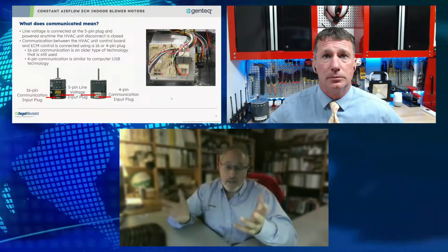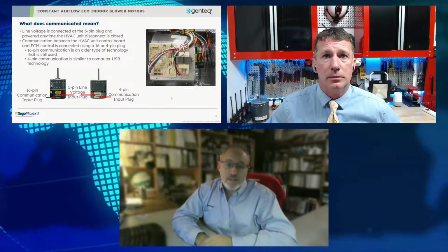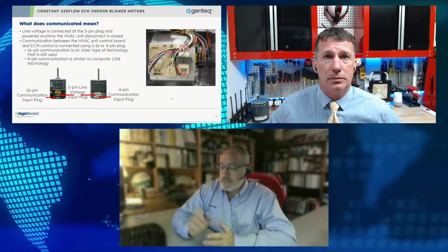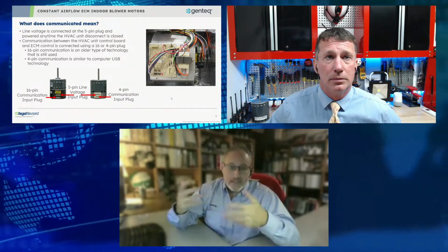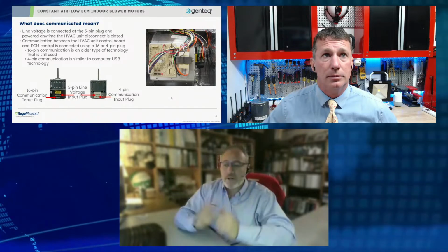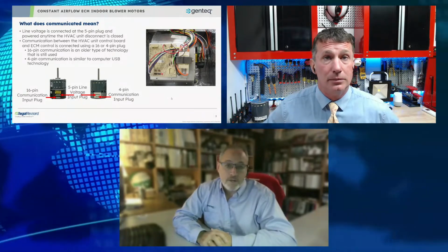But if I want the motor to provide communication back, I'm running, I'm here, what speed I'm running, then I need a transmit channel back. So that's how the current 4-pin motor works. So when you look at the 4-pin motor, again, trying to make things simpler in your minds, not those big scary ECMs. Just think about a motor with a 5-pin plug and a USB port, because that's really all that 4-pin plug is.